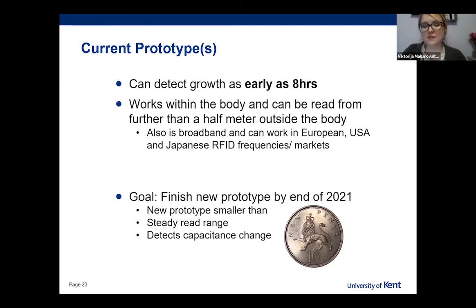The issue with this, if you look at the paper, is that it's the first prototype, so it's not as user-friendly as I would like. It still relies on read range and frequency shifts to determine what the capacitance is. So I'm like, okay, this can't be very usable for clinicians. So there's a new prototype that I'm working on that is actually smaller than this one. I can't show it to you, sadly, because of the publication rules. But it'll be smaller than a 10 pence coin. It has a steady read range because it has its own embedded capacitance shift. That just means it can adjust and read when there's a shift in capacitance rather than needing a shift in frequency.